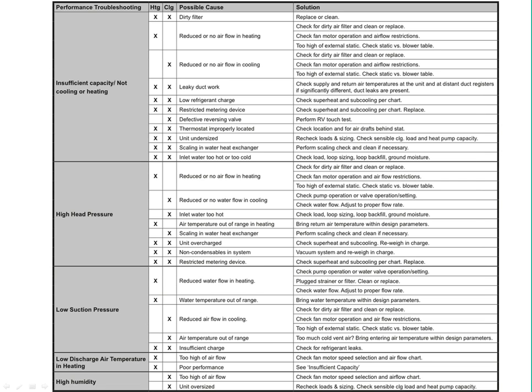If the heat pump's delivering everything it can, well, either your ductwork doesn't have the ability to deliver it. We covered that in part one of this webinar. Could be that the load of the house is insufficient, or the unit was undersized. So typically it's a delivery or a load issue in that project. So that's typically what I see.